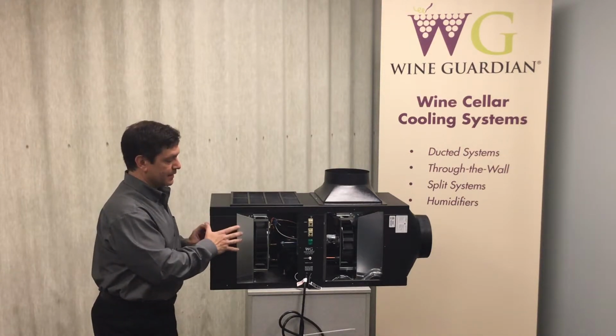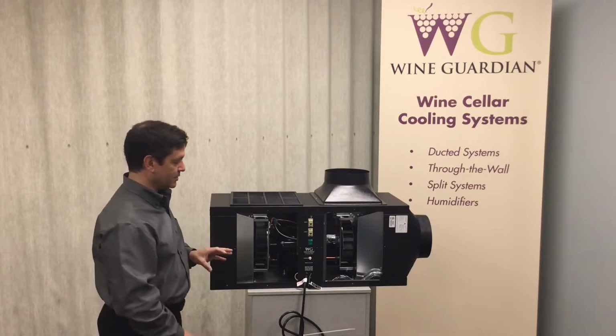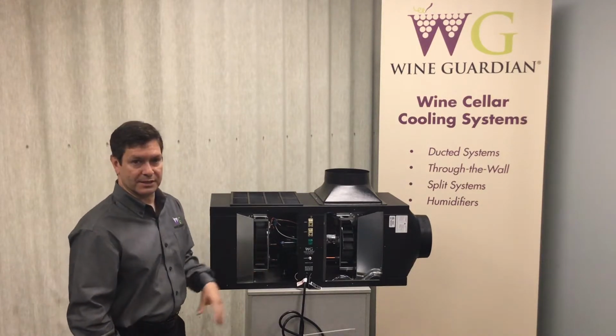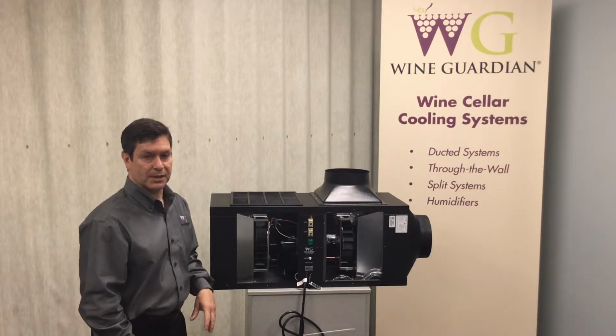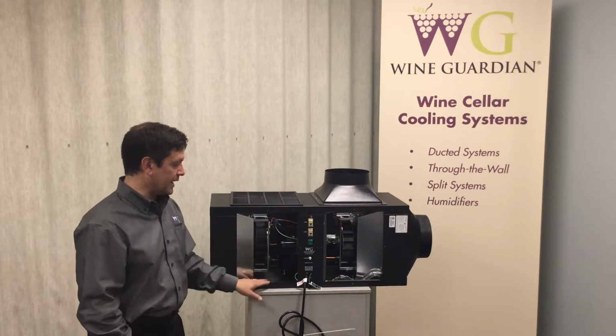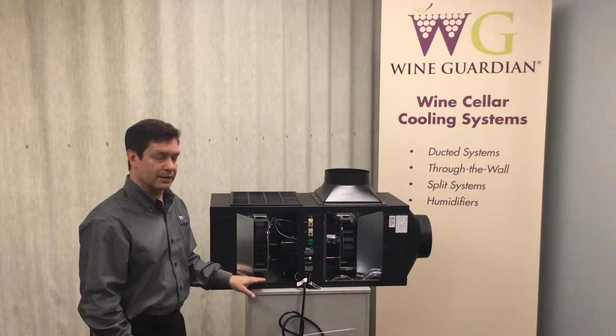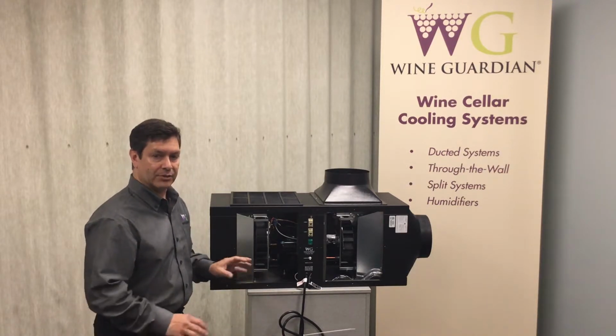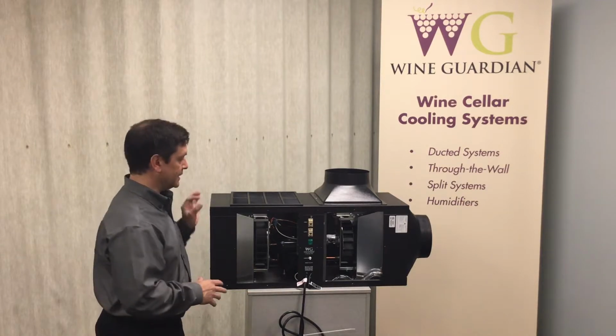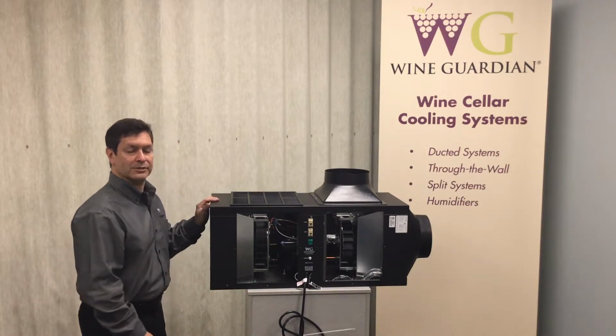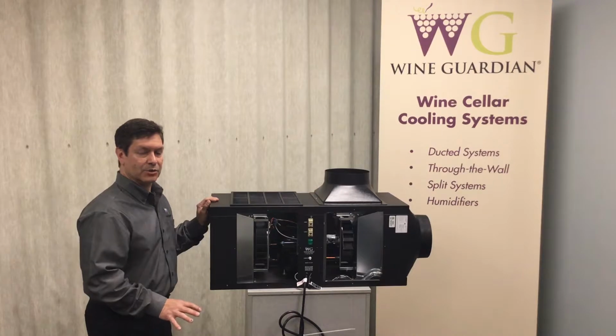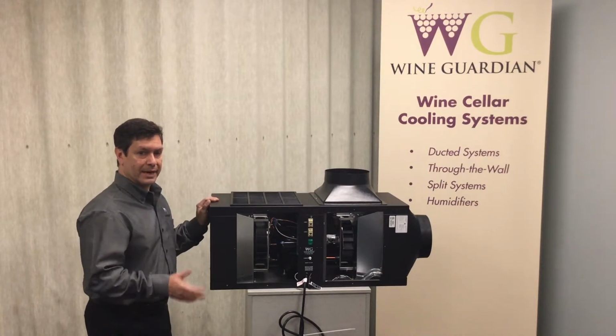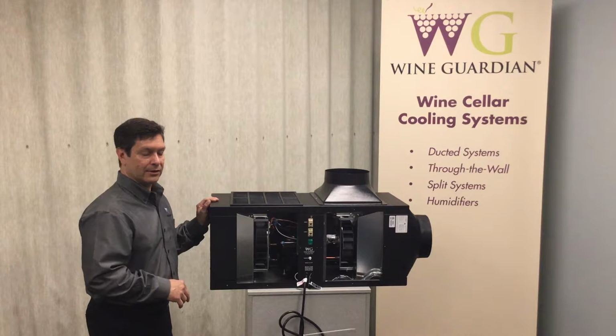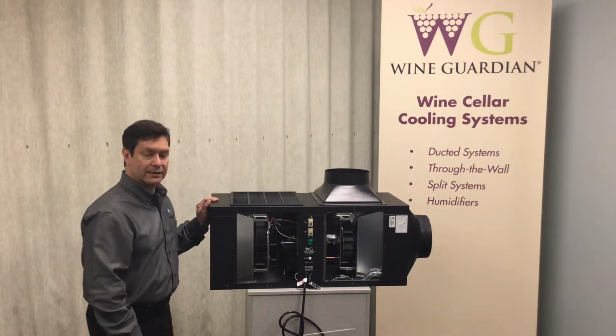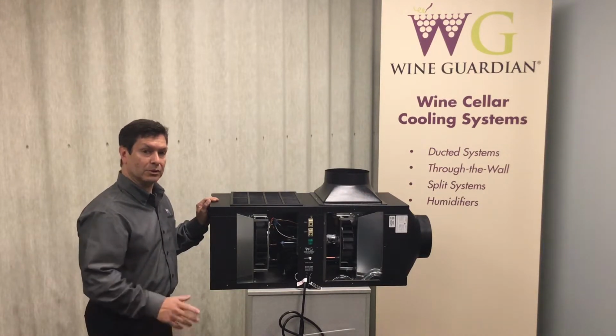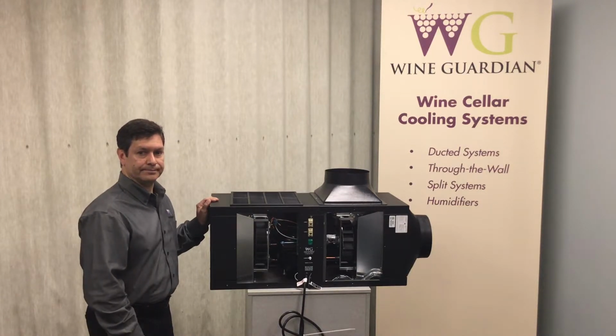Okay, that's a factory installed option. It has to be installed at the factory because of the two devices that I mentioned earlier. All right. So when you're applying our self-contained unit, be considerate of where it's being mounted, how it's going to breathe essentially on the condenser end, and if you need to bring in air from outside. If you need to bring in air from outside, understand the maximum and minimum conditions of that air, and you will have to look at low ambient protection if they're below 40 degrees Fahrenheit.